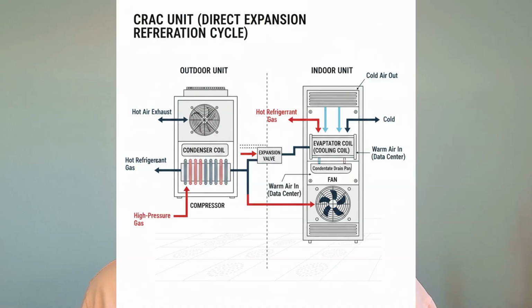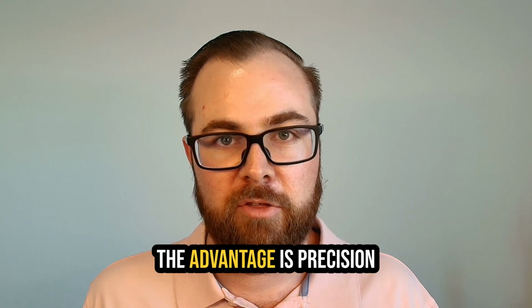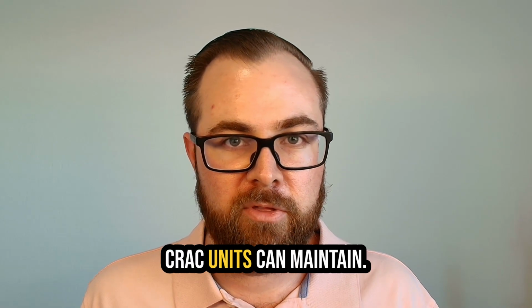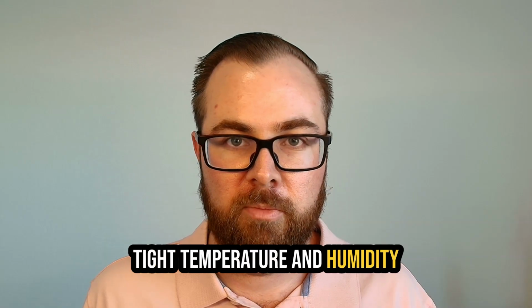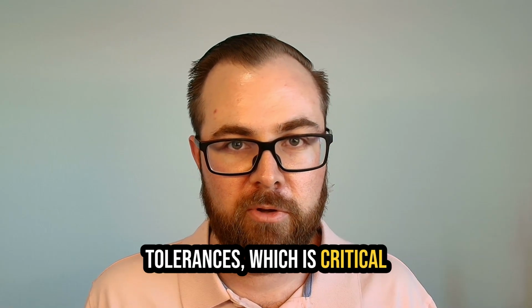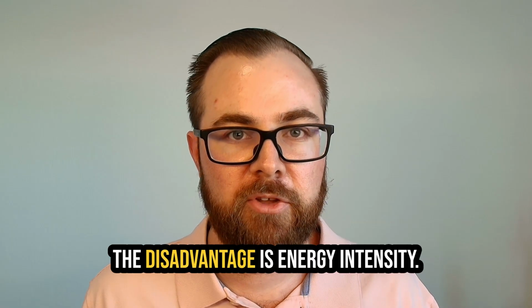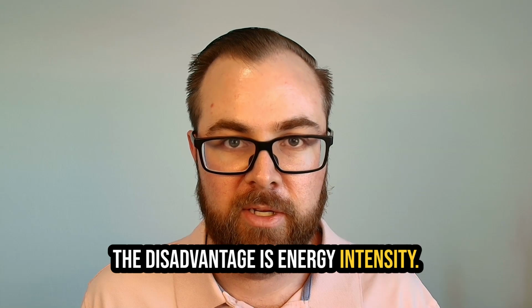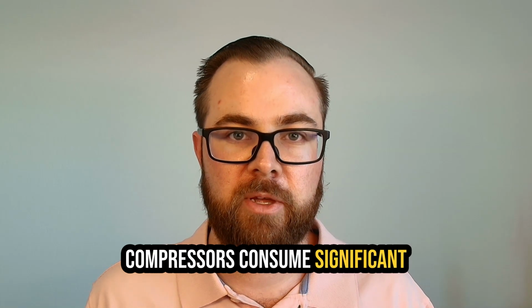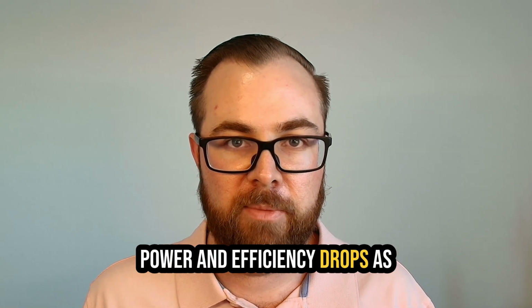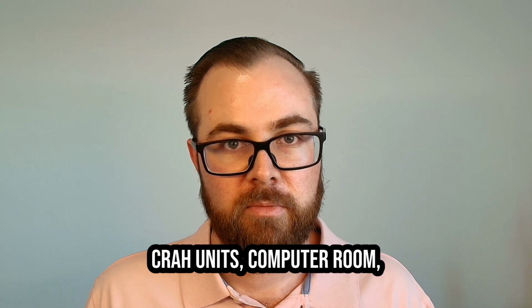Refrigerant evaporates in the cooling coils, absorbing heat from the air, then gets compressed and condensed outside the data center, releasing that heat. The advantage is precision. CRAC units can maintain tight temperature and humidity tolerances, which is critical for sensitive equipment. The disadvantage is energy intensity. Compressors consume significant power, and efficiency drops as ambient temperatures rise.